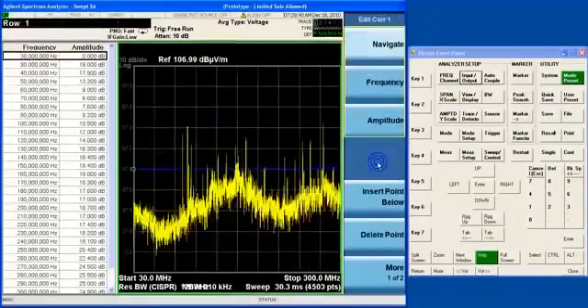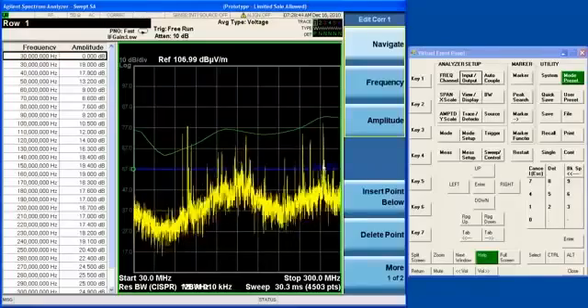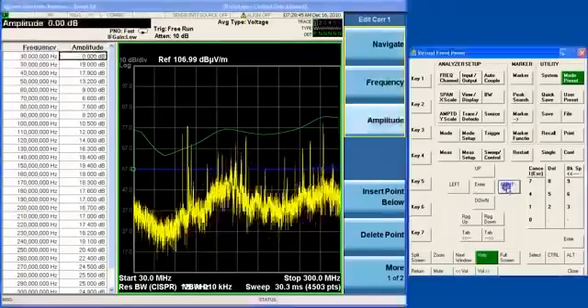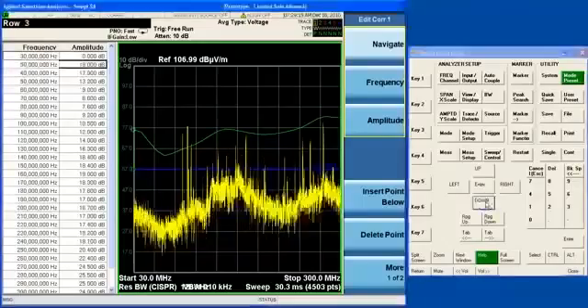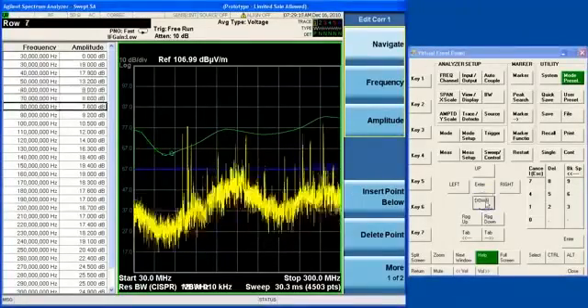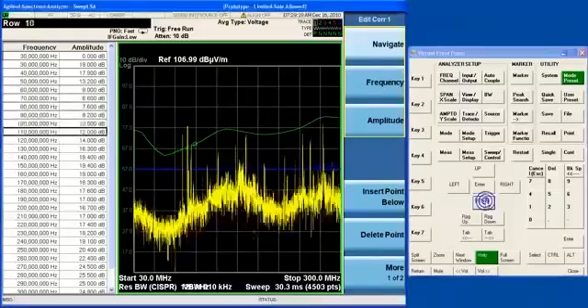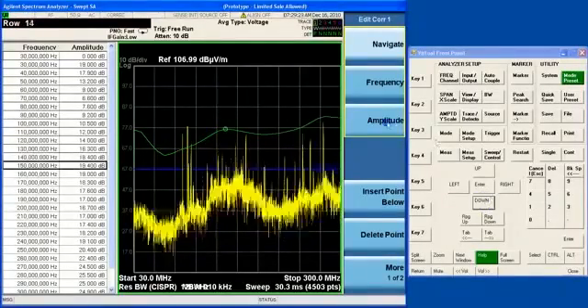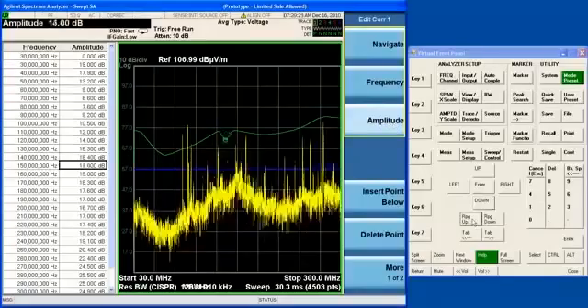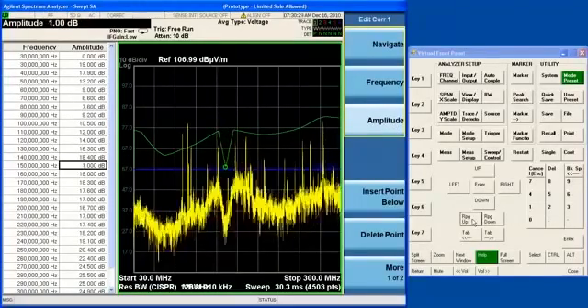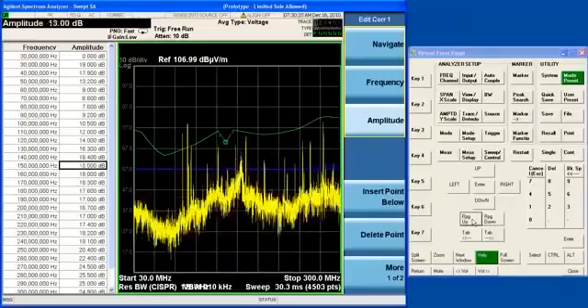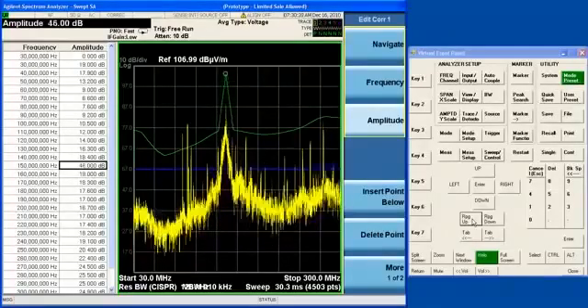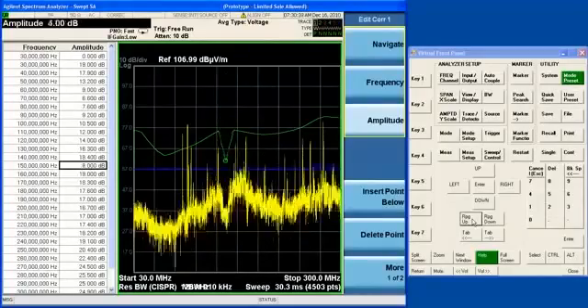You can even edit the correction factor using Agilent's advanced correction editor. You can see that as you move through the correction table, the little cursor follows you across the screen. And you can get to any particular point and easily edit the amplitude of that point. I am turning the knob to show you how easy it is to edit data in the corrections table.